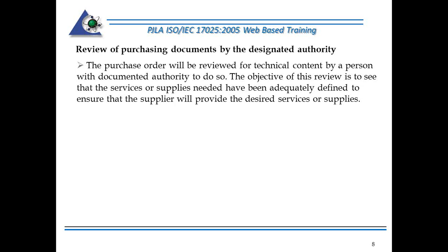The best way to approve that would be perhaps they initial or sign their signature to the purchase order or to the copy that a company, the laboratory, would retain. So there's a record that yes, it's been examined and approved, possibly dated and signed. But the point for laboratories to recognize and remember is the responsibility is yours to build into your procedure the method defining how this is done. How is this approval performed, and how is it documented? And as I said, I would suggest that they sign and date a copy of the purchase order indicating that they've approved it.